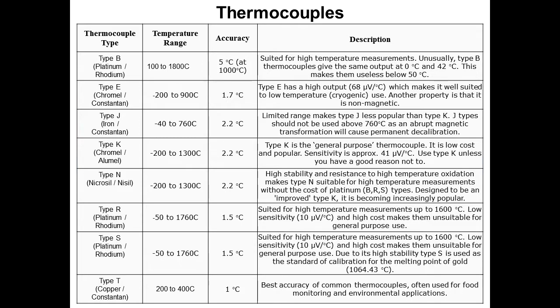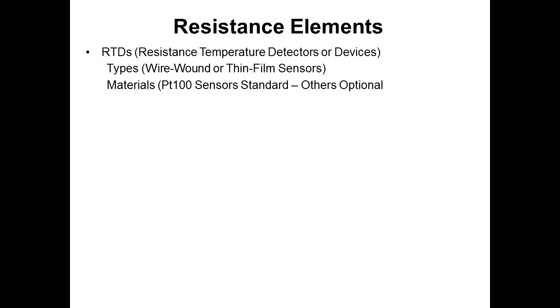They generally won't work very well down low because of the voltage required. And here a Type B gives the same output at 0C and 42C, so they're worthless below 50C. So these are specialized applications. A lot of people are starting to replace Type Ks with Type Ns. It's a little more expensive, but it's more stable and offers improved accuracy.